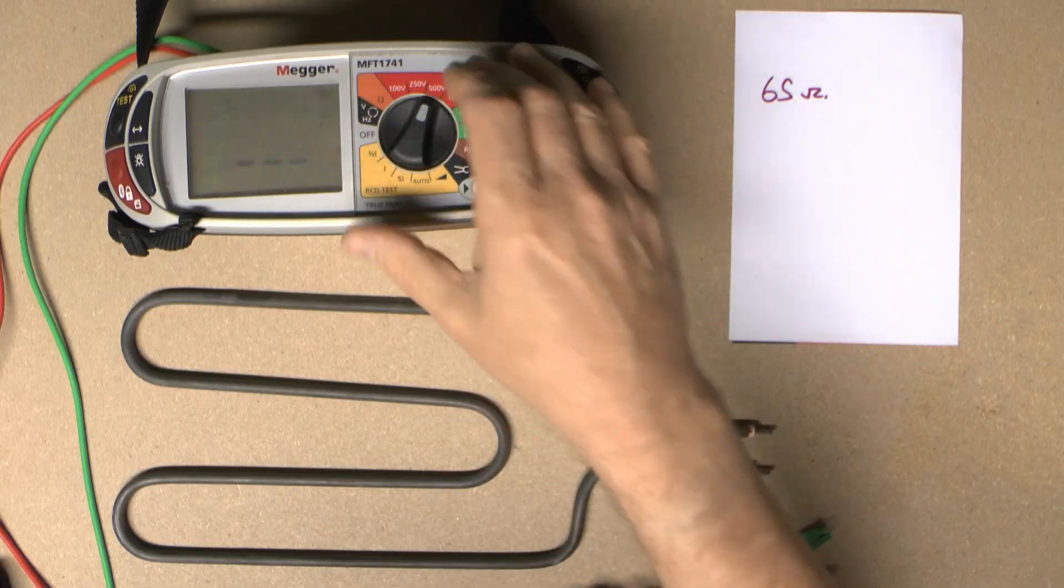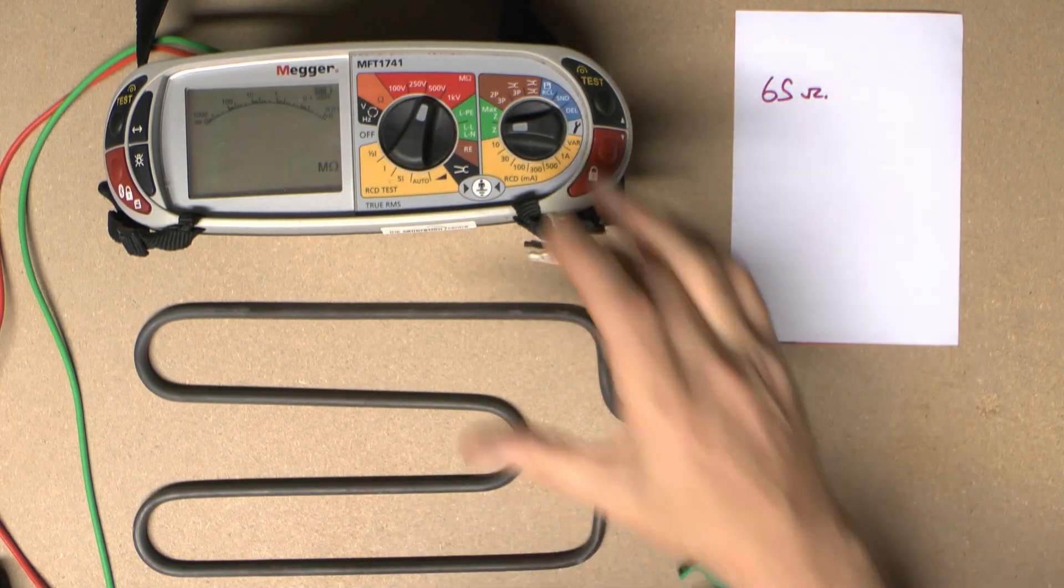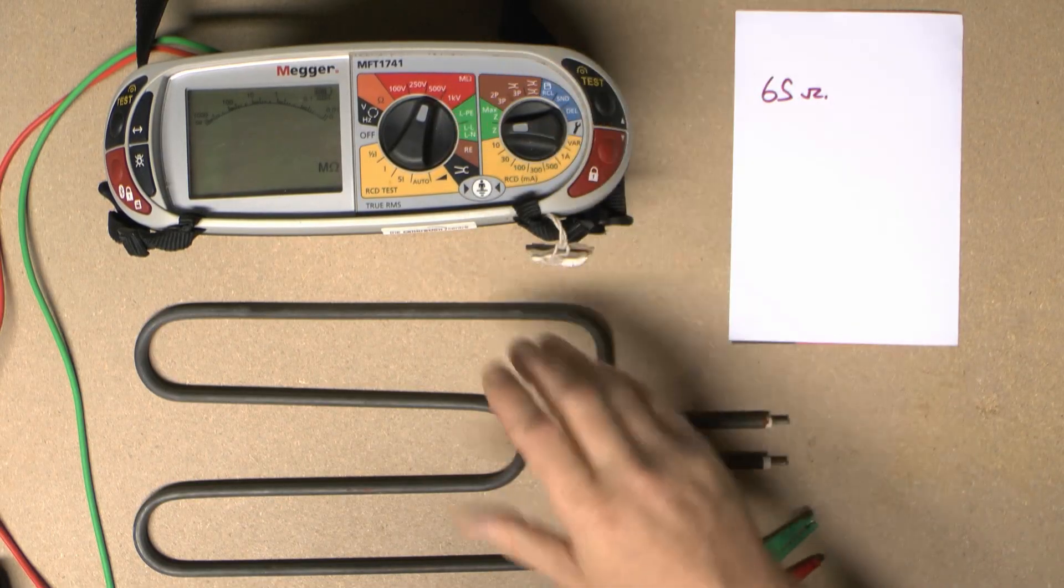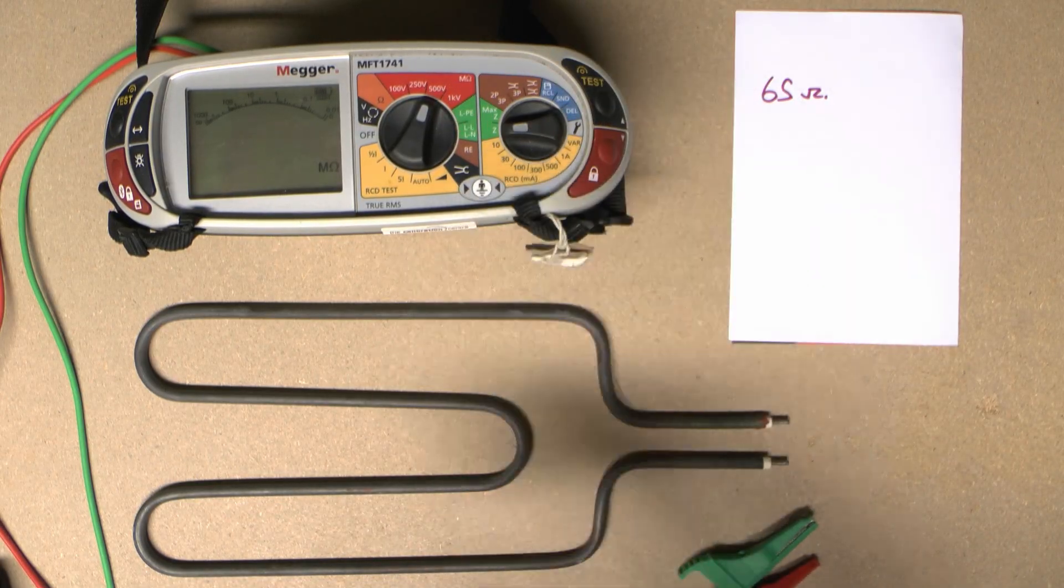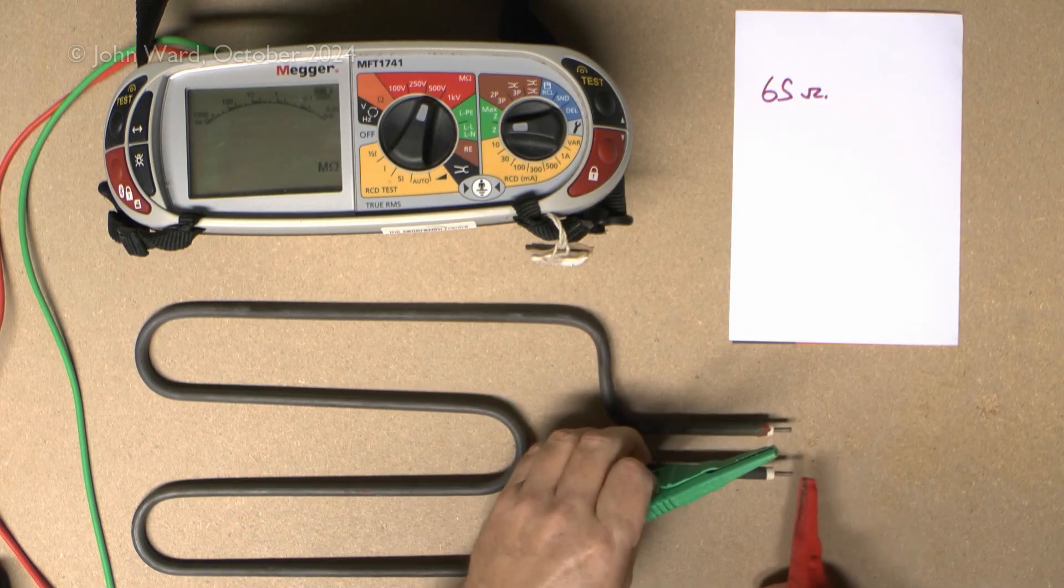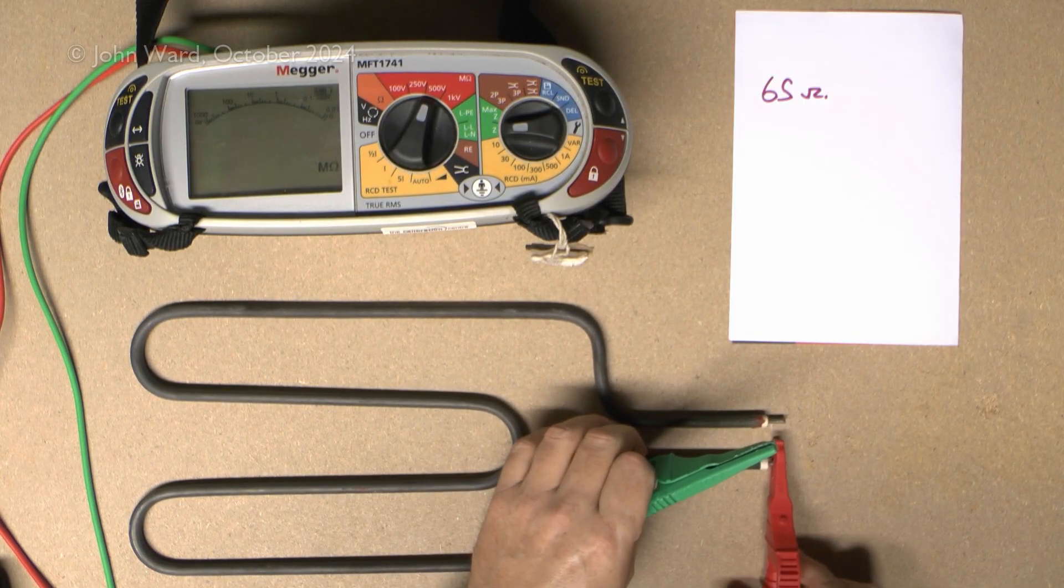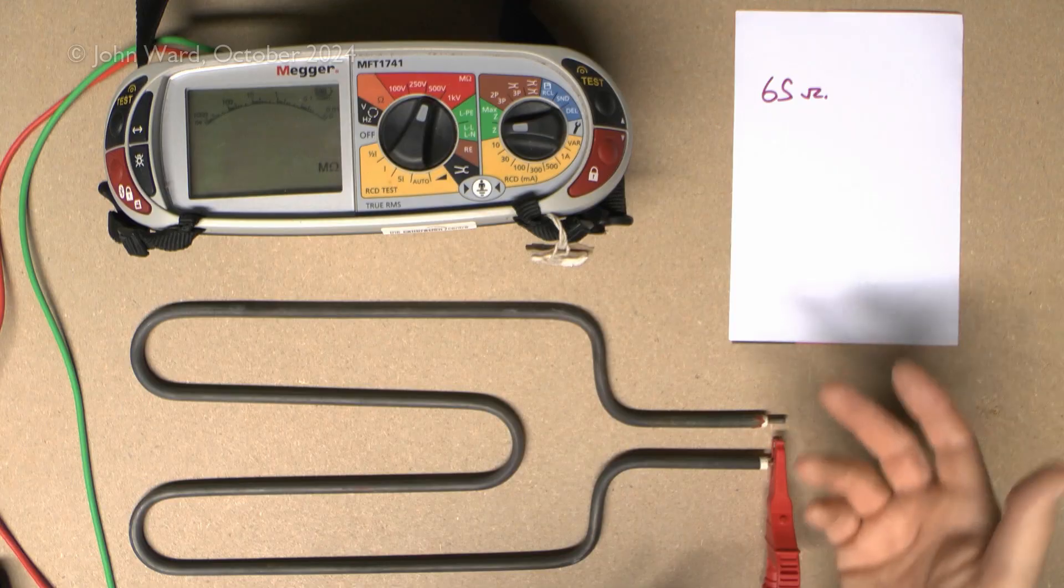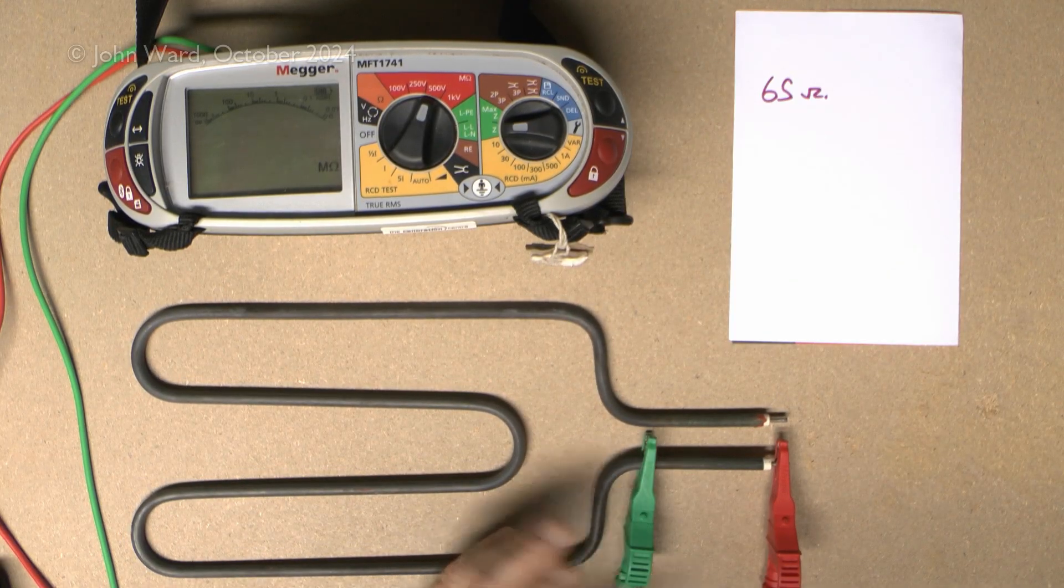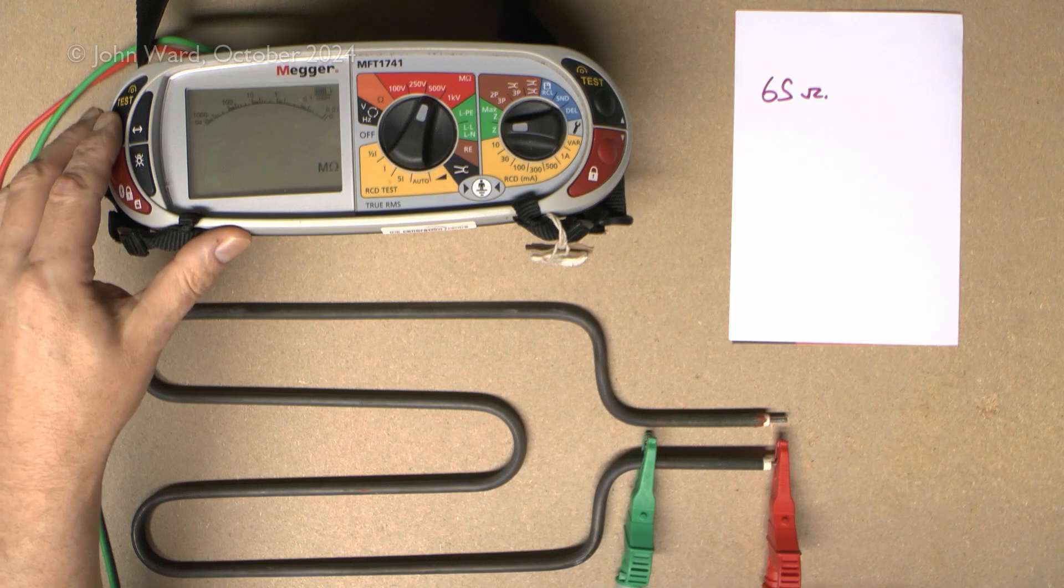The other test is insulation resistance. Just like testing insulation resistance of a circuit, we're going to use the 500V range. This is a 230V element, so that's appropriate. We'll connect between one of the pins—doesn't matter which one, because we just checked there was only 65 ohms between them—and then the metal covering at some point. Then we can test that.